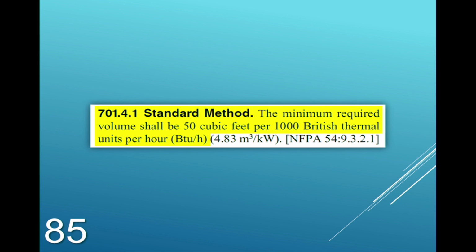So do you agree? This guy tells me, hey Wade, if you'll give me 50 cubic foot for every 1,000 BTUs you have, fire it up. Don't cut any holes anywhere. We're good to go.